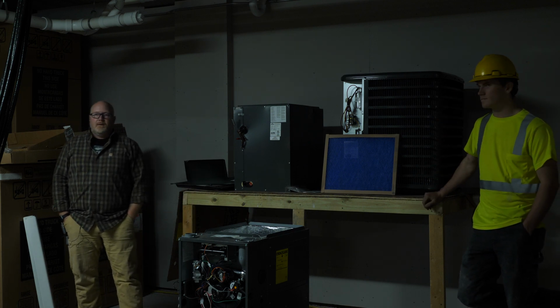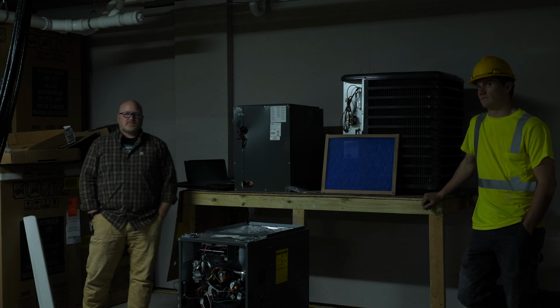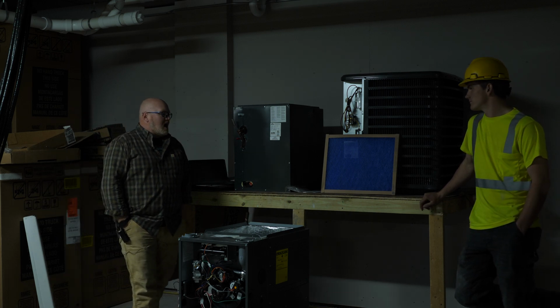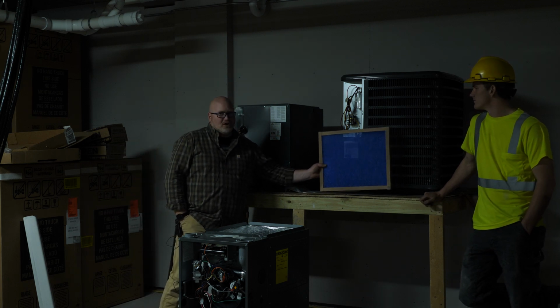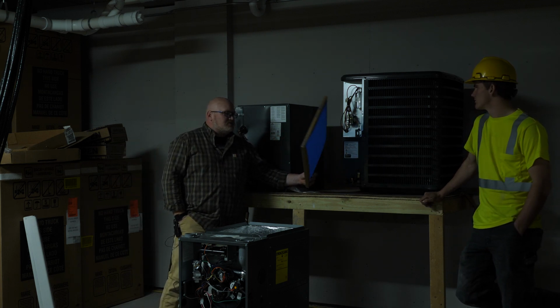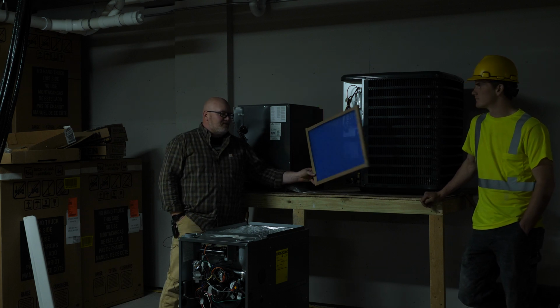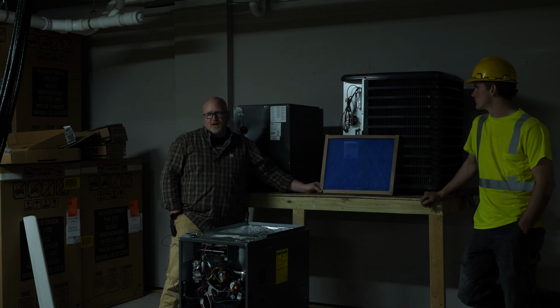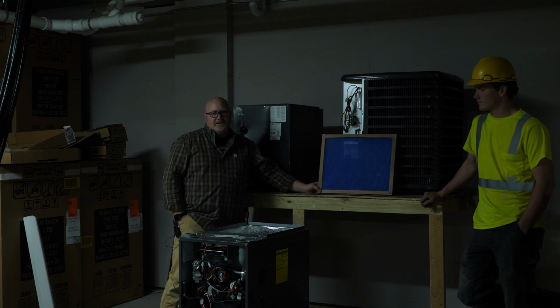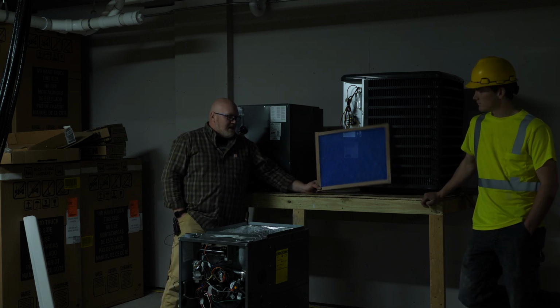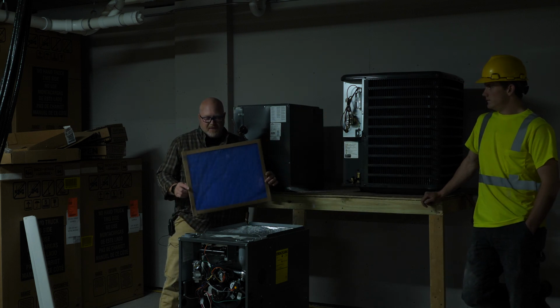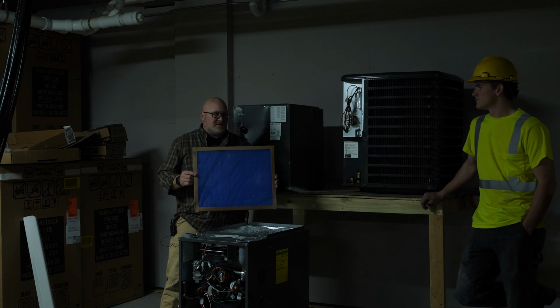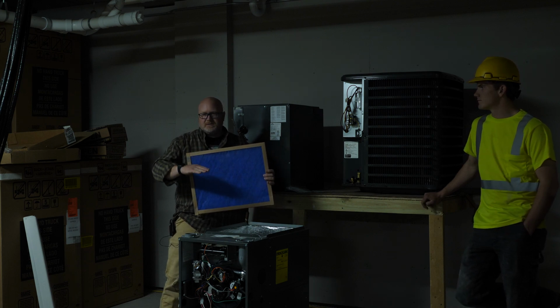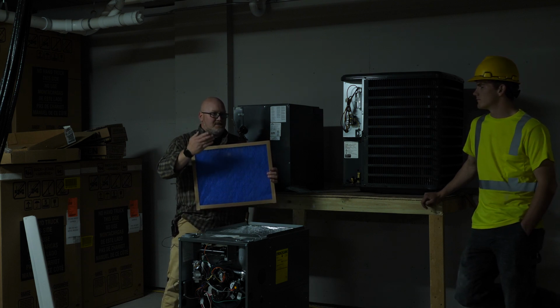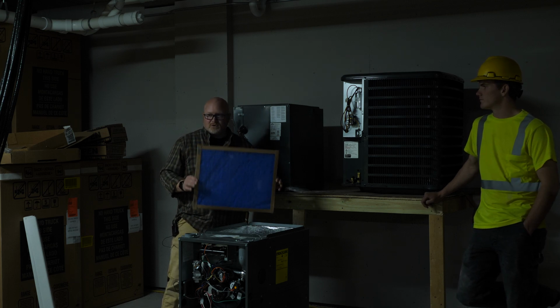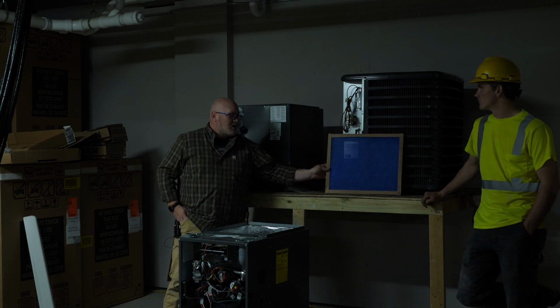Change the filters. You have a blue filter there. Is that the kind of filter you recommend over the pleated style? Good question. I consider these construction filters. These are just a light media filter. I would not recommend these. Spend a couple extra dollars and get what's called the deep pleated media filters. They make them in 1 inch, 2 inch, up to 4 inch. When I say pleated filter, it's basically a filter media that is pleated, and they do that to get more surface area out of your filter.